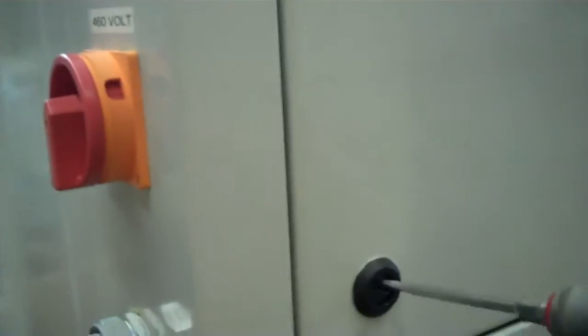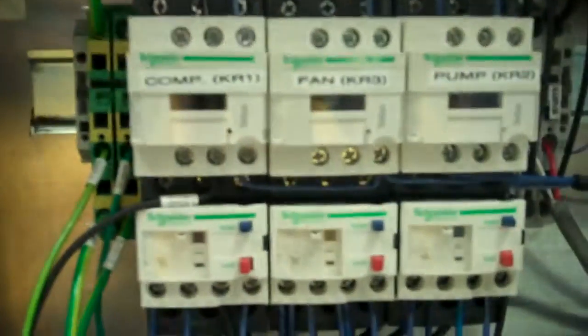Now all these systems, again, we put in all new controls. You have our contactors and our overloads for the compressor, the fan, and the pump, all adjusted at the factory. And all these settings are documented in the manual and startup guide that we provided. It's three-phase power, 460 volt to power the whole system. The controller power is actually 220 volt single phase. So this here is a transformer to take one leg of the 460 power at single phase and step it down to the single phase power needed for the controller.